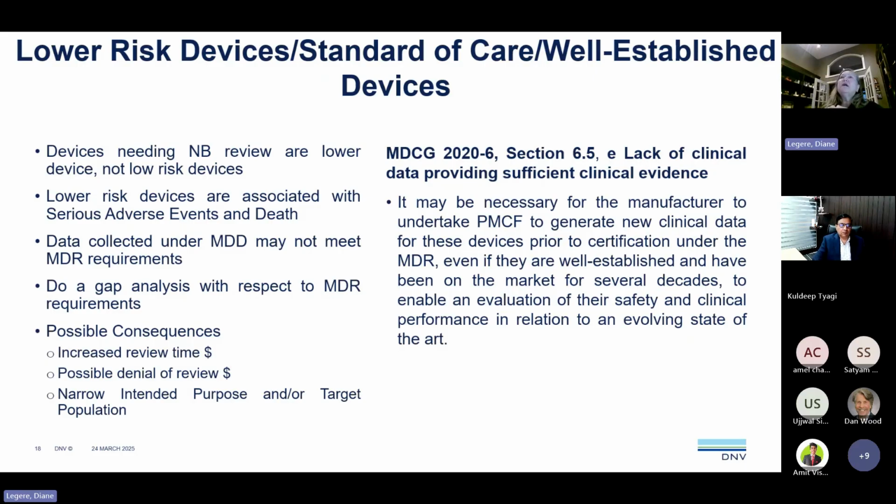I'm going to say the ones that have come close to denial by me have been lower class devices, because of all the things I just said, they just did not pay attention to the gap between MDD and what they had for MDR. You might have to narrow your intended purpose or your target population, because there's no data on your device.